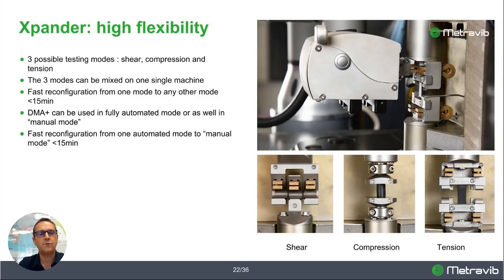The DMA+ can be used in a fully automated mode, or can also switch to a classical manual mode. According to the design, it's quite easy to continue to use the DMA without the robot if there is any need for R&D work on different geometry or different configuration. And the reconfiguration from the automated mode to the manual mode is also limited in terms of time, below 15 minutes.